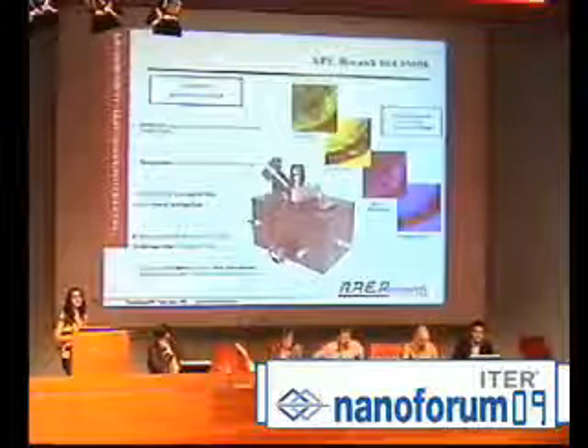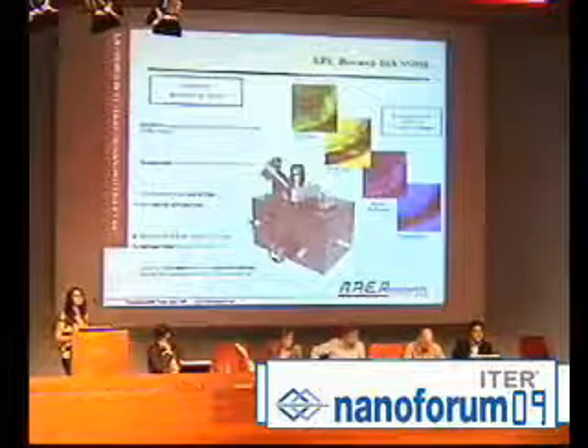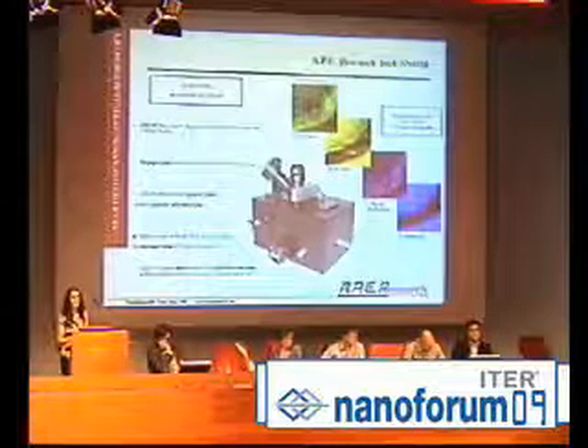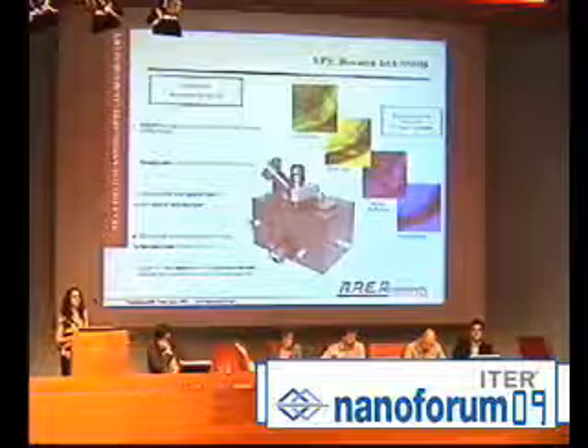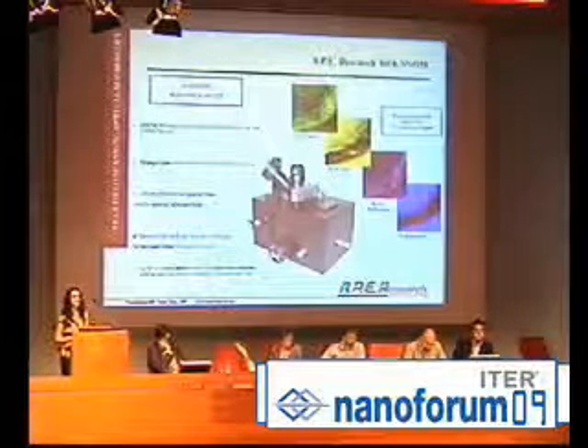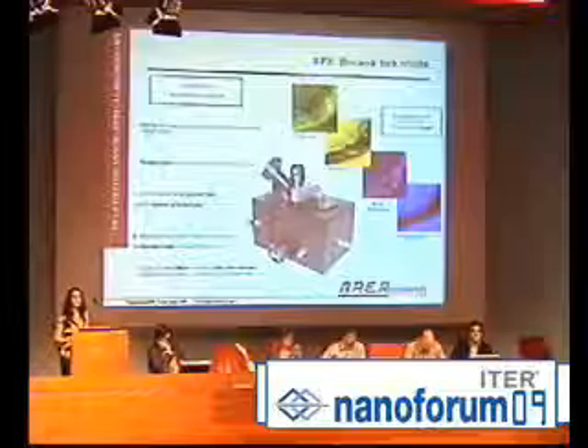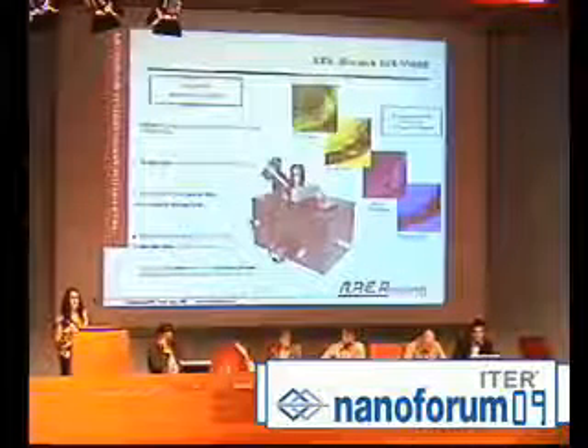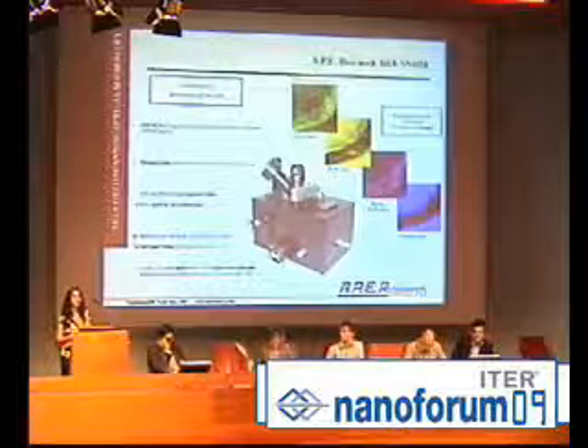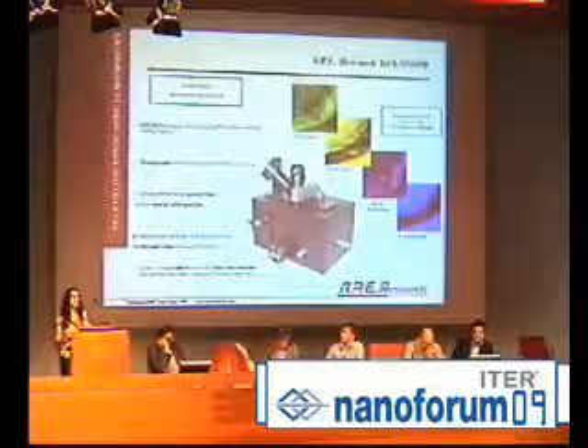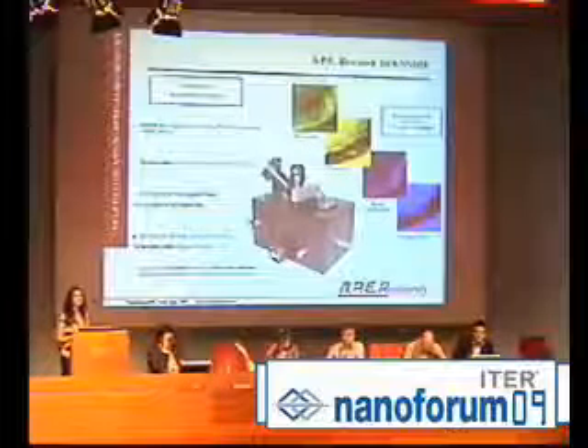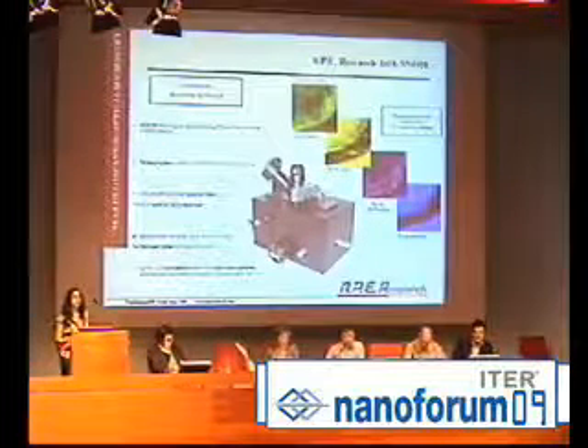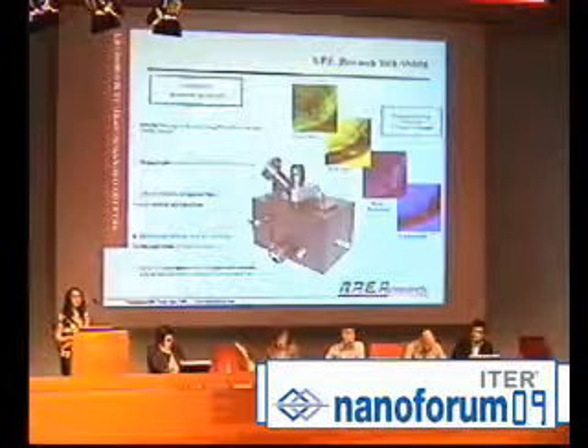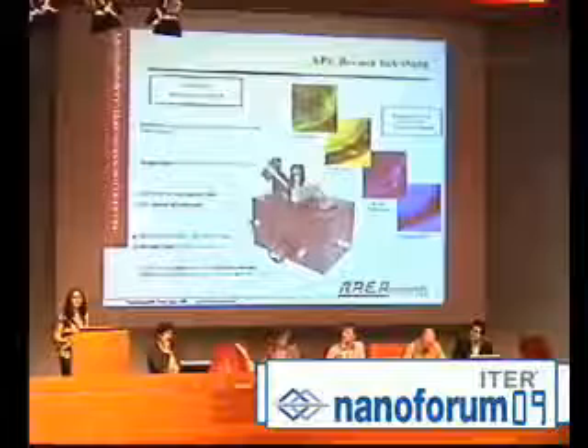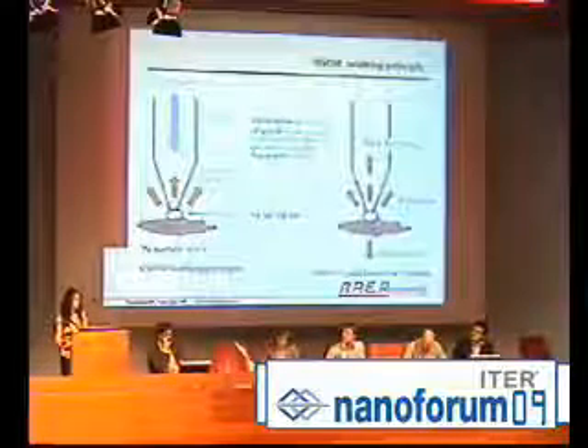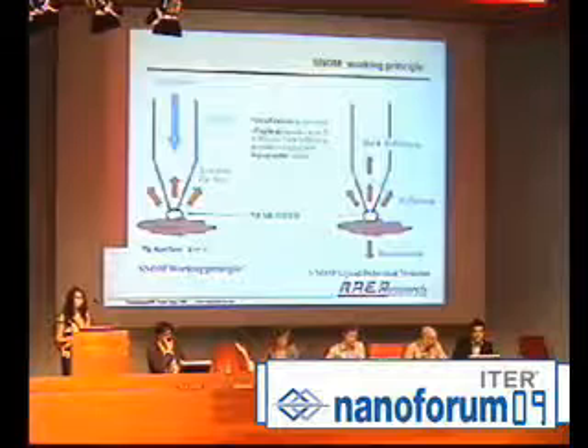SNOM is a particular SPM technique because it has a particularity in the probe. The probe is an optical fiber, so this technique can combine the SPM topography, like in AFM, and the optical information from the sample. And this optical information presents a very high resolution. With the near field, we can overcome the diffraction limits that all traditional, conventional optical microscopes have. This is a schema of the working principle of SNOM.